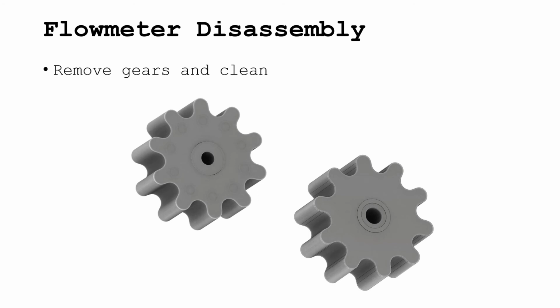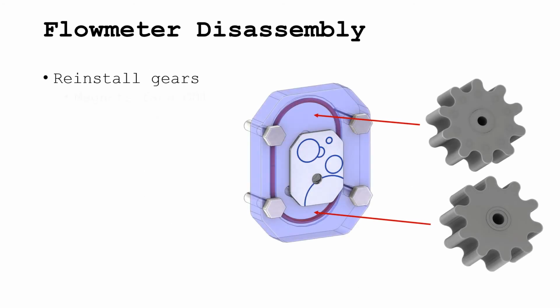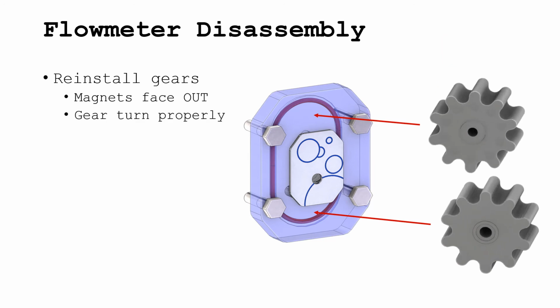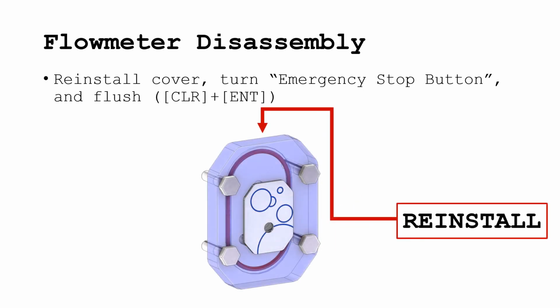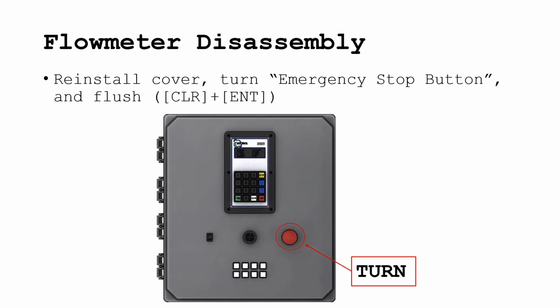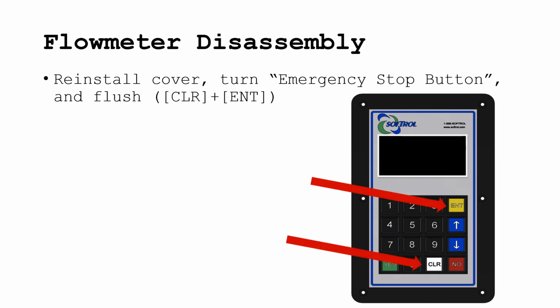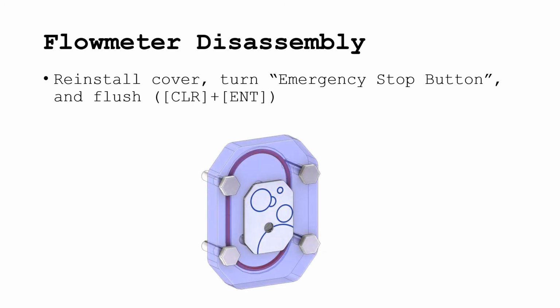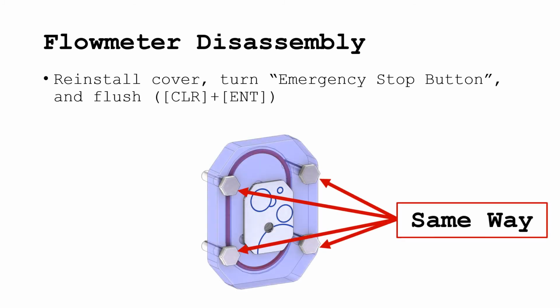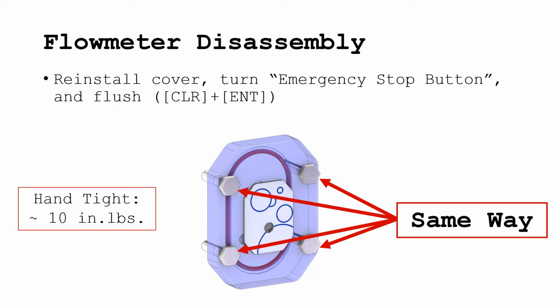Remove the gears and check for debris. Reinstall the gears. Make sure the magnets on the counter gear are facing out and the gears turn properly. Reinstall the cover. Rotate the emergency stop button. And flush the manifold thoroughly. Note, reinstall the cover the same way you took it off, using a nut driver and making sure it's hand tight, about 10 inch-pounds.